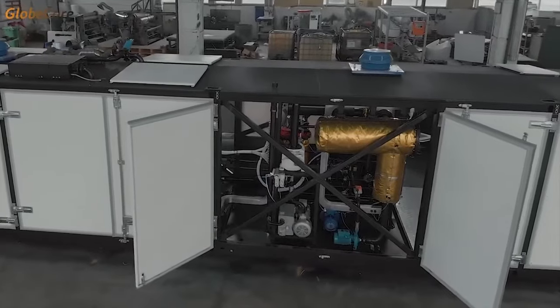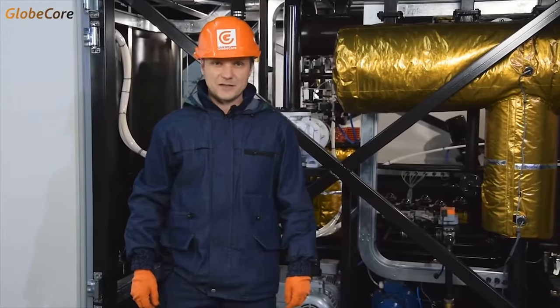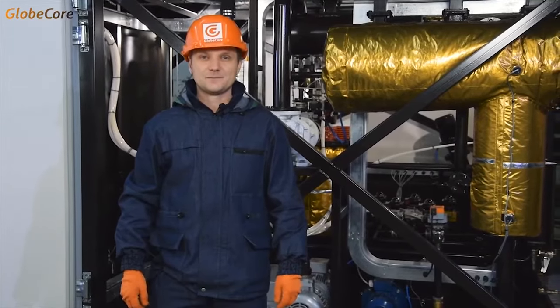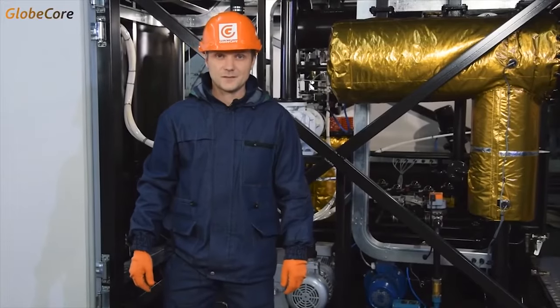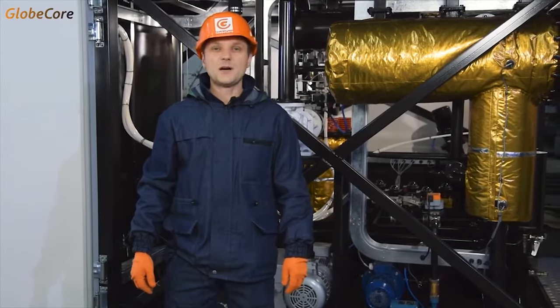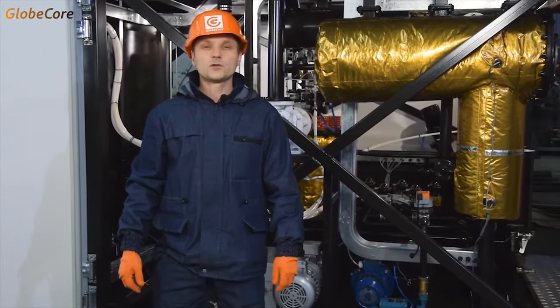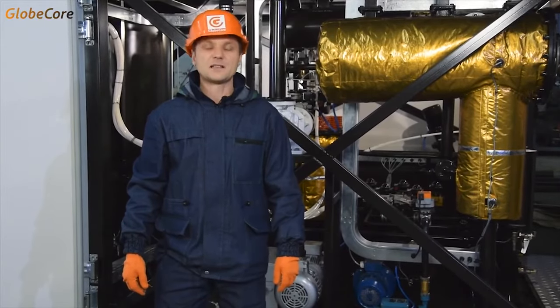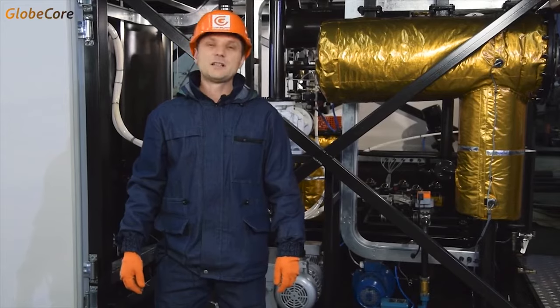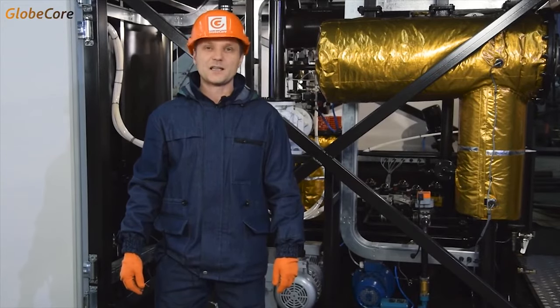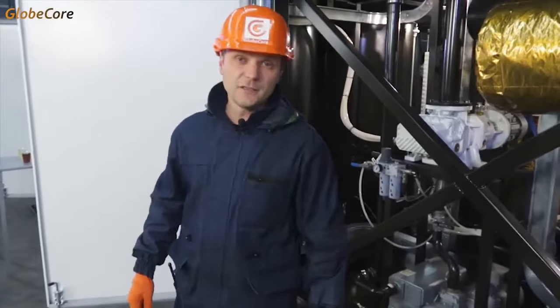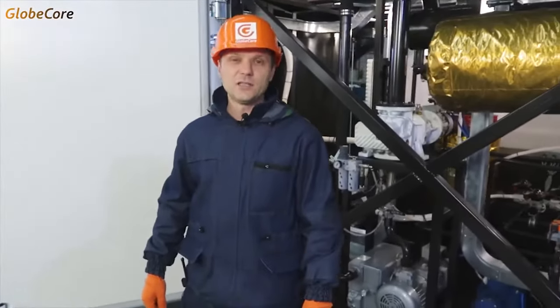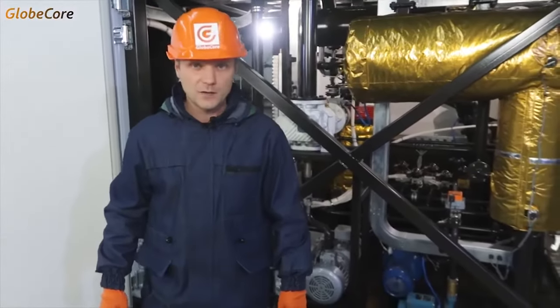The main idea the CMM-6R is based on is to extend transformer lifetime by regenerating transformer oil. The idea is to periodically process the oil in the transformer, restoring its quality to the level of new oil. It's important to note that this does not equal changing the oil periodically. Let me explain why. Suppose you drain the old oil and fill the transformer with new oil. What happens next? Of course, when we drain the oil, we remove the products of oil aging contained in that oil, but only that specific part of the contaminants. Everything that we want removed from the transformer still remains in its components and immediately contaminates the new oil, which is thus no longer new.